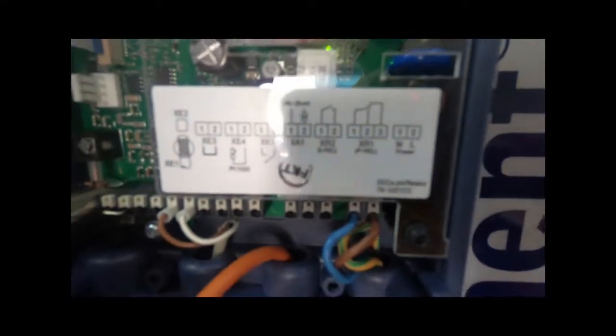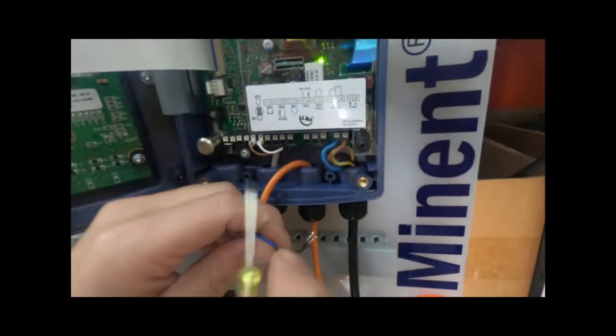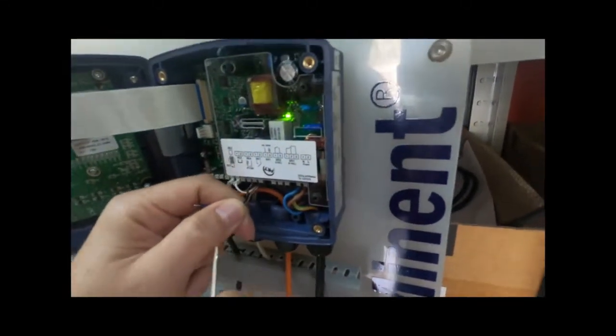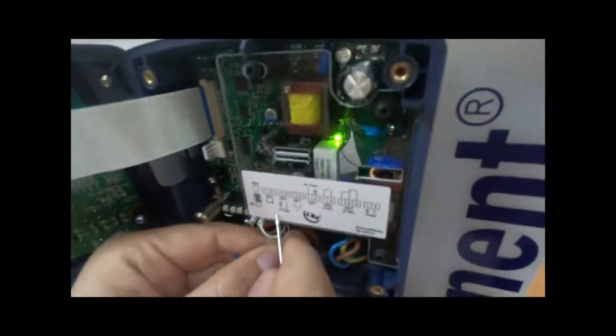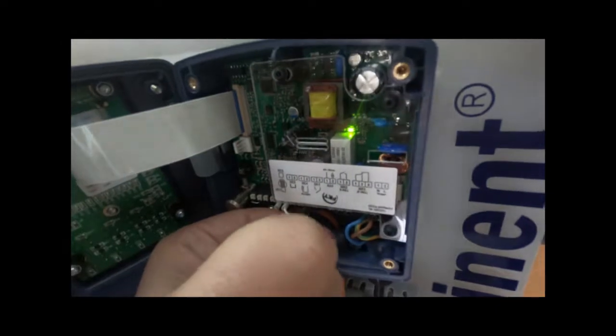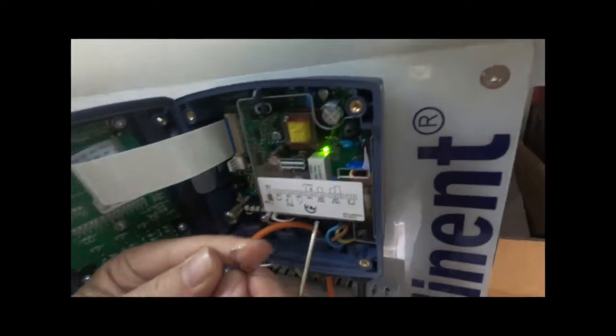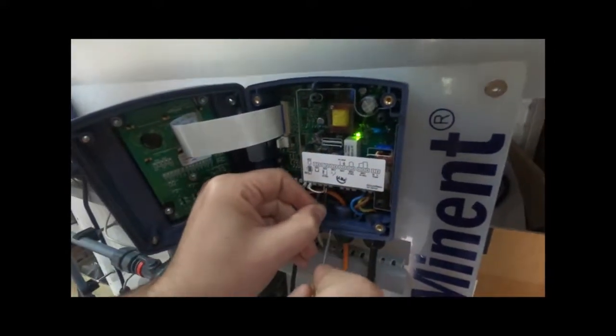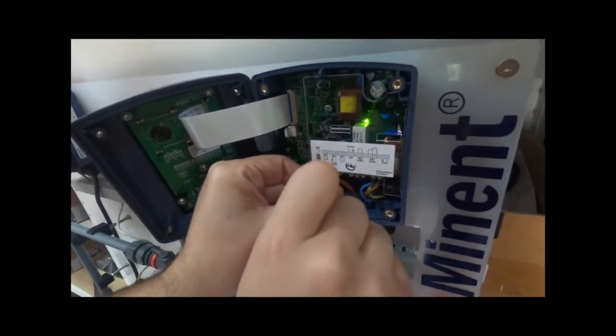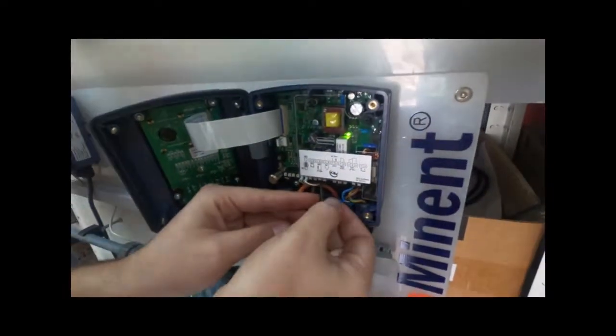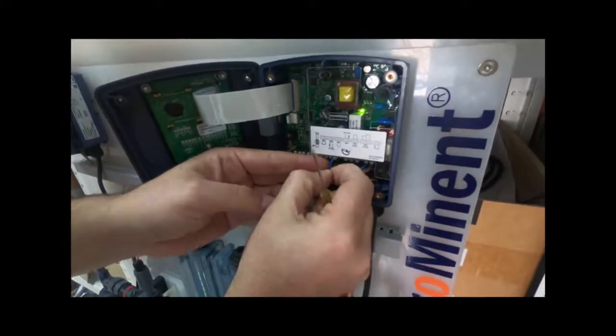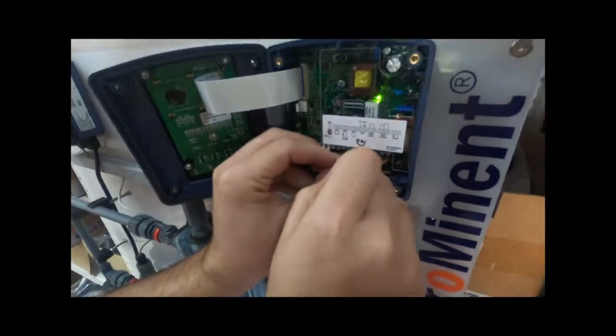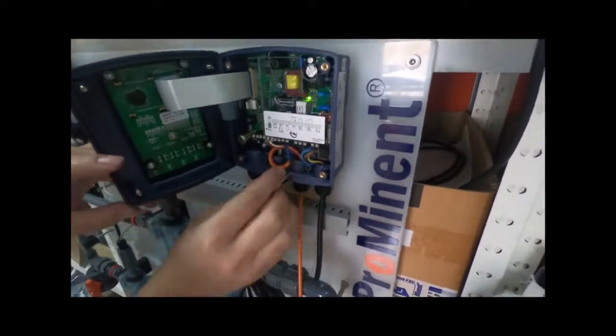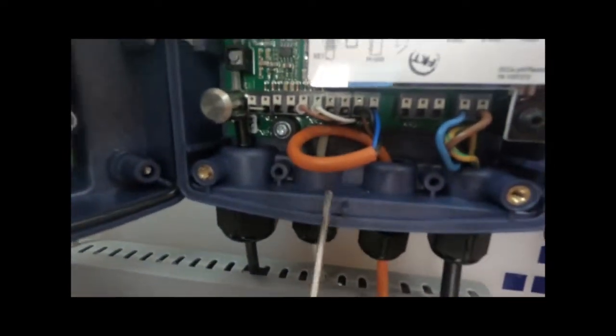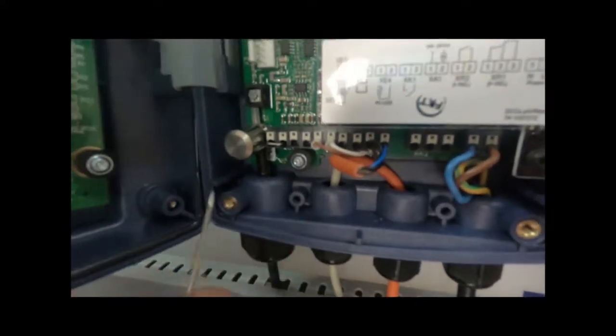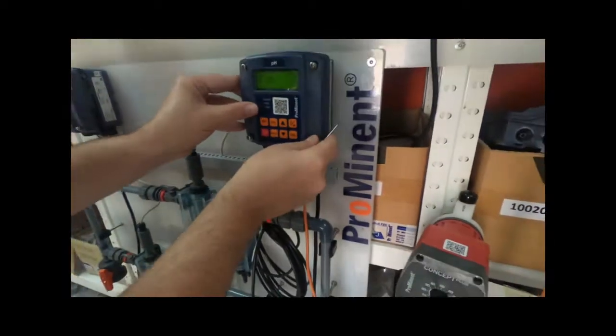So here we will connect the black and the brown together, and we'll go to the XR2, which is this one. We'll put both together in number 1, which is this one. We'll just press the white button here and push both cables inside. And the blue in terminal number 2. So that's pretty much the connections that we have: the power, the control cable for the pump, the flow switch, and the sensor control cable. So we'll close it.